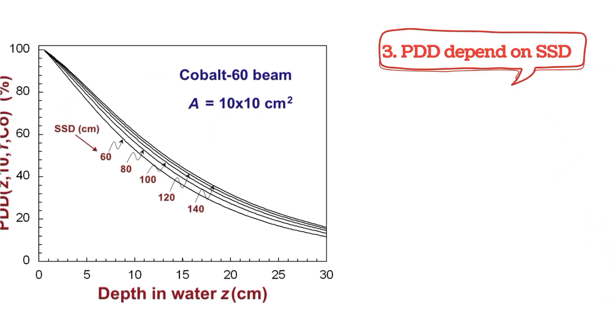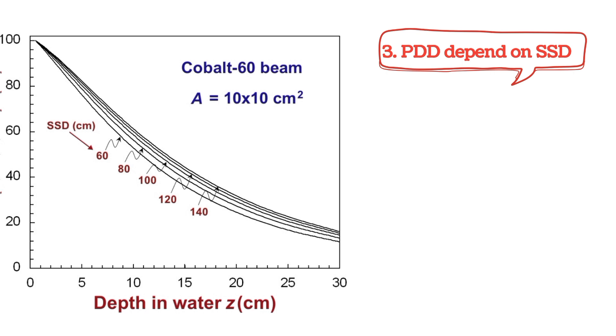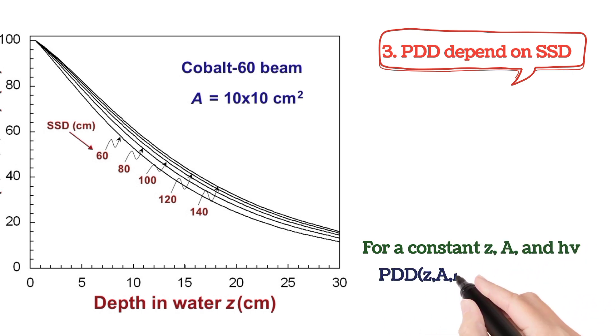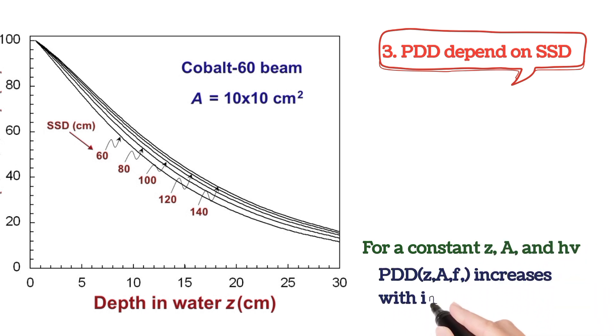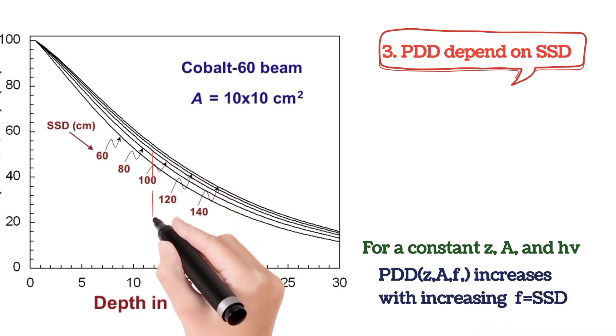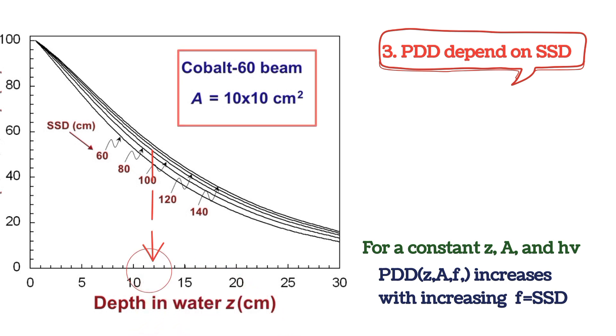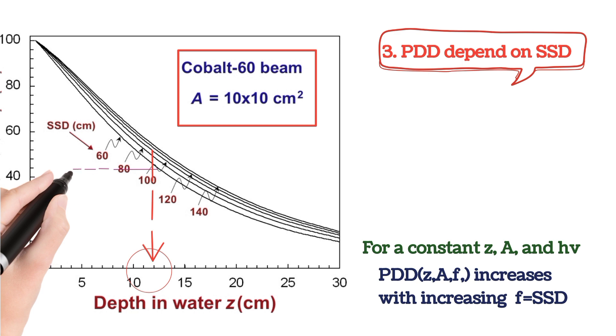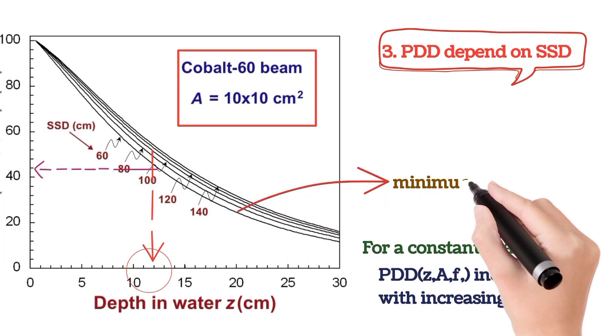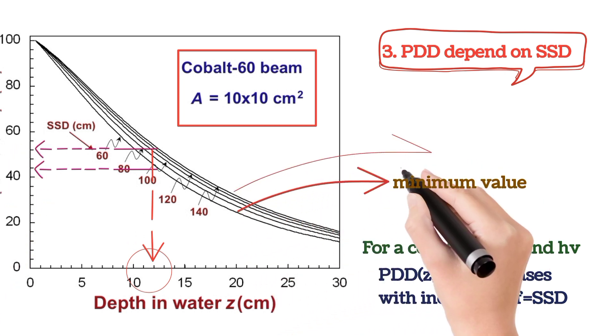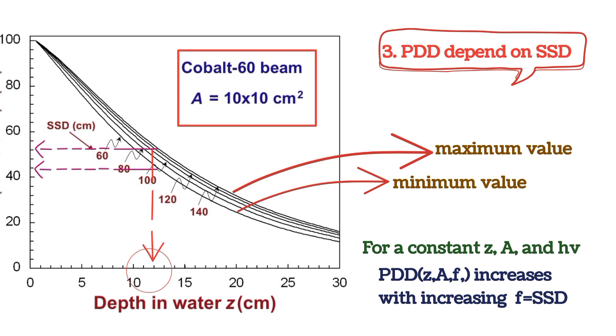We see how PDD depends on SSD. For a constant depth, field size, and energy, PDD increases with increasing SSD. At a constant depth, constant field size, and constant beam energy, smaller SSD has minimum PDD value and higher SSD has maximum value. PDD is directly proportional to the source-to-surface distance.